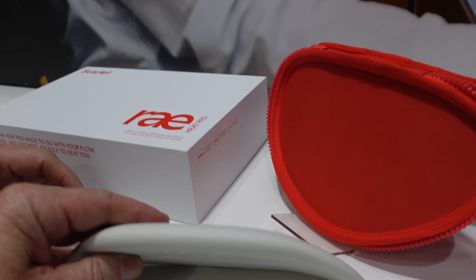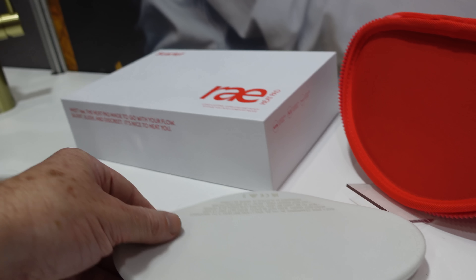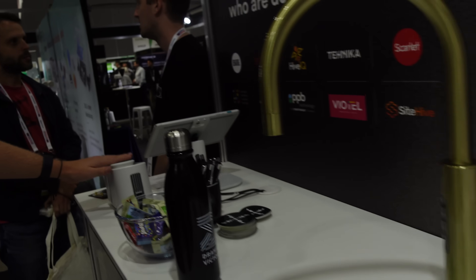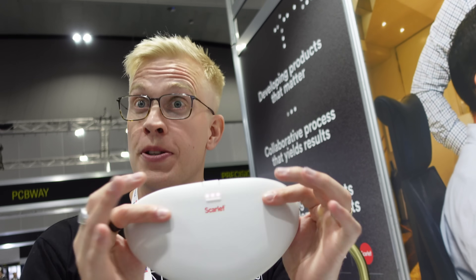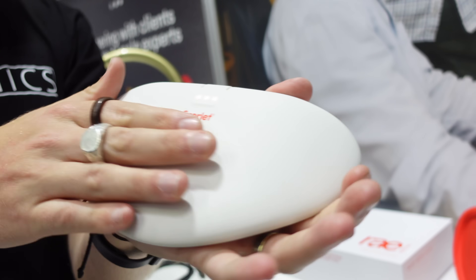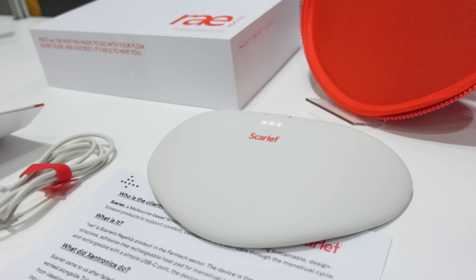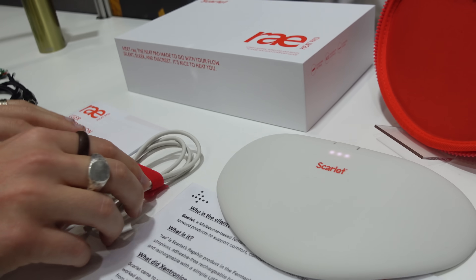The shell is silicone. We did the electronics inside. A company called Trike — they're a design firm based here in Melbourne — did the industrial design. We don't have industrial design in-house; we steer clear of that, focusing more on systems engineering. We did early focus groups and user studies to work out the shape, different prototype colors and sizes. Even the silicone has a specific finish to get that smooth feel — it's food grade silicone. We also helped design and develop the content of the user manual as part of the safety standards.